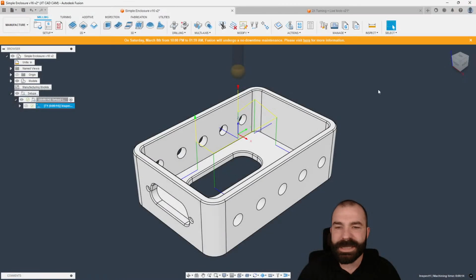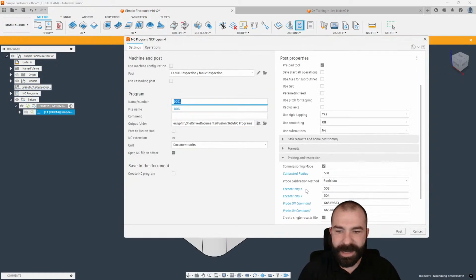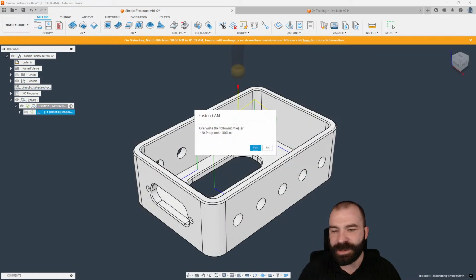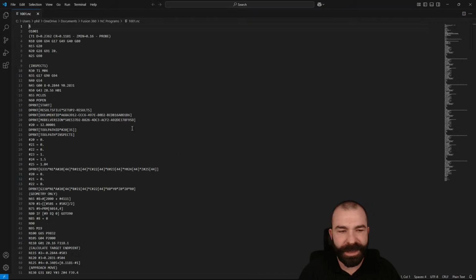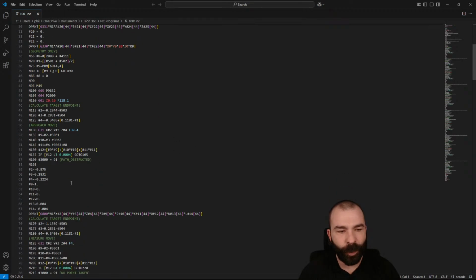But once you run it the first time to make sure you don't tear up $3,000 worth of Renishaws, you can come back the next time you post out your program to run it. And you want to make sure you turn off that commissioning mode, right? So what that's going to do is the second time through, what you're probably going to notice is my code is going to be a wee bit shorter.